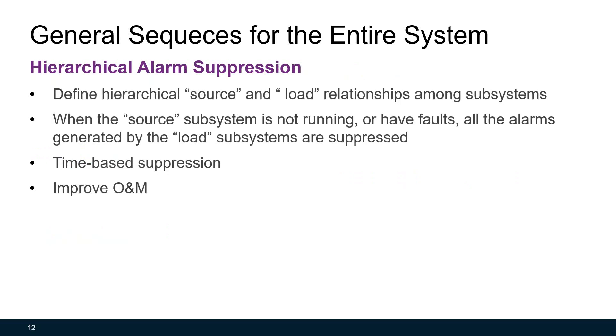The goal of the hierarchical alarm suppression algorithm is to minimize the number of alarms generated. In a forced-air system, the AHU provides conditioned air to the zones, and the VAV terminal units control airflow and temperature to the zones. The AHU is the source and the VAV terminal unit is the load. If anything goes wrong with the AHU, such as fan failures or cooling coil faults, all VAV terminal units may generate many unnecessary alarms. The alarm suppression algorithm will suppress these alarms, improving HVAC system operation and maintenance.